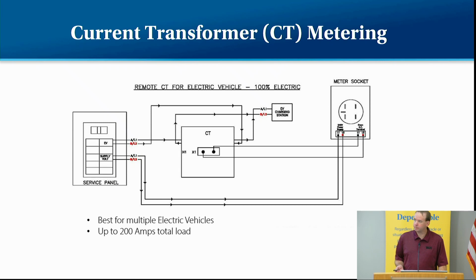What's the benefit either way? So the benefit of the direct metering, if you just have one EV, is you run your EV circuit to the meter, and from the meter to your EV, you don't have the additional equipment. The benefit of the CT metered, you can have more than one EV. Depending upon your location, if it's going to be difficult to get the number 6s outside and back in, you just have to run a number 14 and a number 12 from the CT box inside out to the meter socket. So it's a lot easier to run that smaller wire than it would be to run number 6 or number 4.